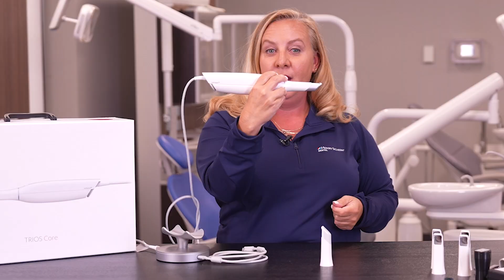But with this scanner, I can actually take the tip off. I flip the lens, and then I slide it into place. So now my power button's still on top. I'm still ergonomically correct, and it makes scanning that maxillary arch a breeze. This scanner is gonna scan about 1,400 images per second, and that's a little bit less than their latest version, the Trios 5 scanner, and that's gonna scan about 2,400 images per second. I don't think that you're really gonna notice that much difference in your scan time when you're actually in the operatory, but I do like to mention it.